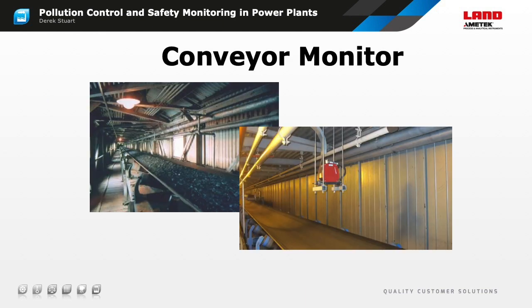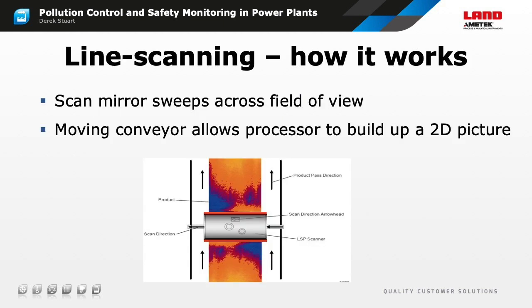Here we see an AMETEK Land HotSpotIR infrared line scanner mounted above a coal conveyor. This is a variation on a thermal imager and is specifically designed to map the temperature of a moving object such as a belt. The scanner has an 80-degree field of view, so the height above the belt should be a little more than the belt width divided by 1.6. Line scanning uses a single infrared detector and a rotating mirror that repeatedly scans across the moving object perpendicular to its direction of travel. The combination of a scanning mirror and the linear movement of the conveyor allows the signal processor to build up a two-dimensional map of temperature.